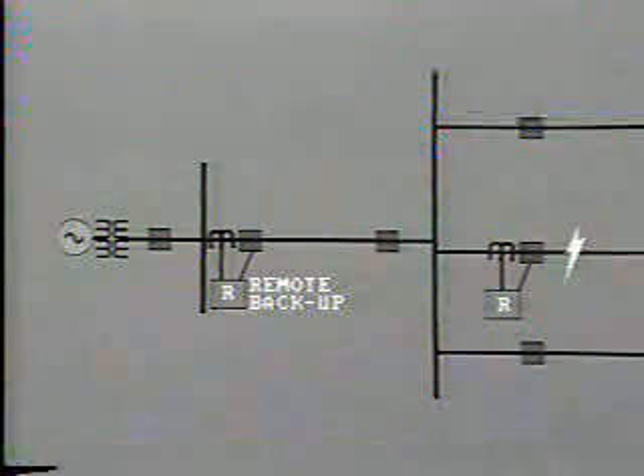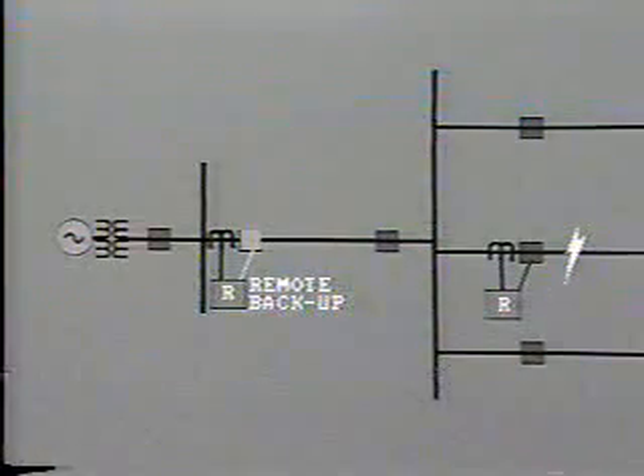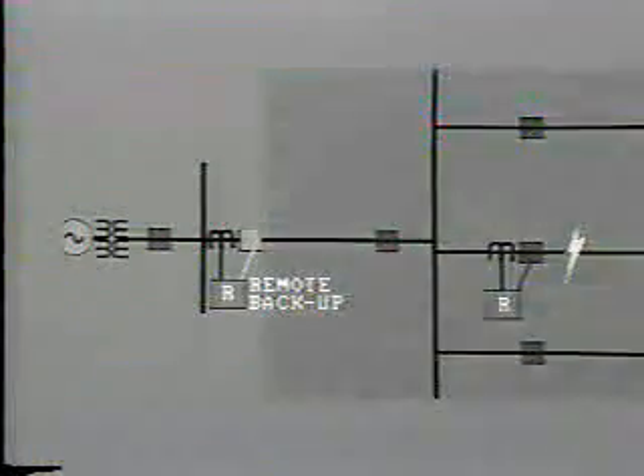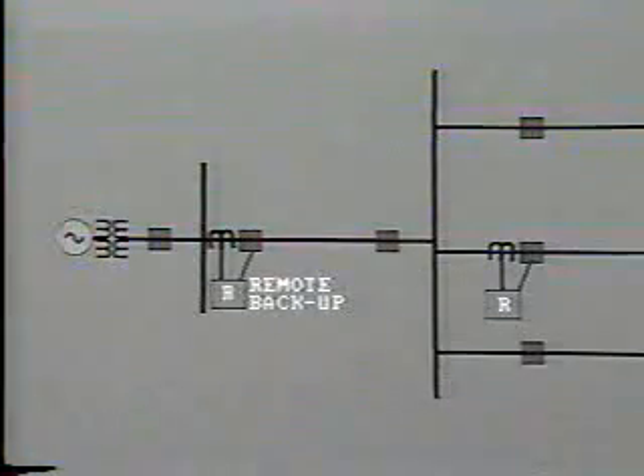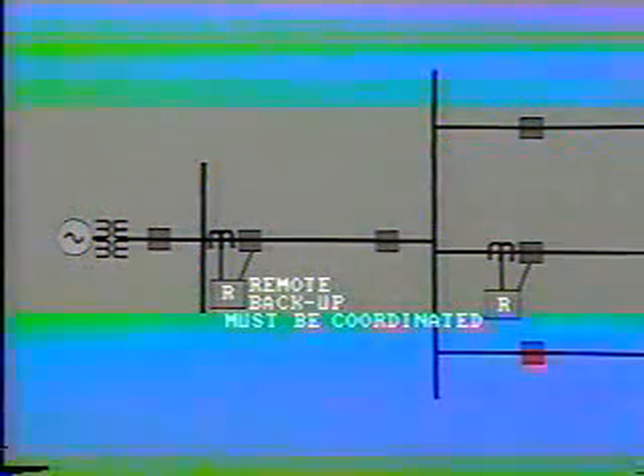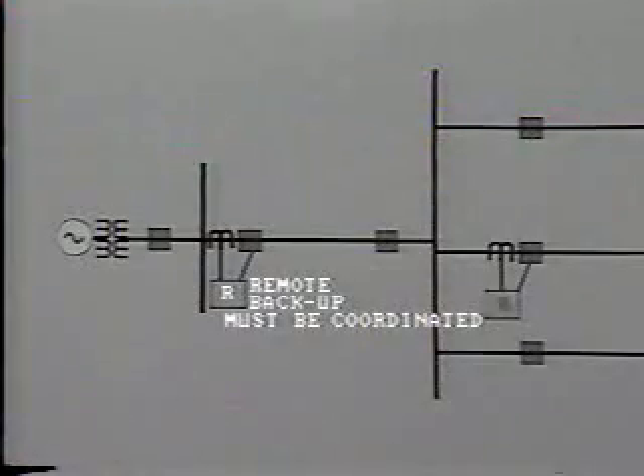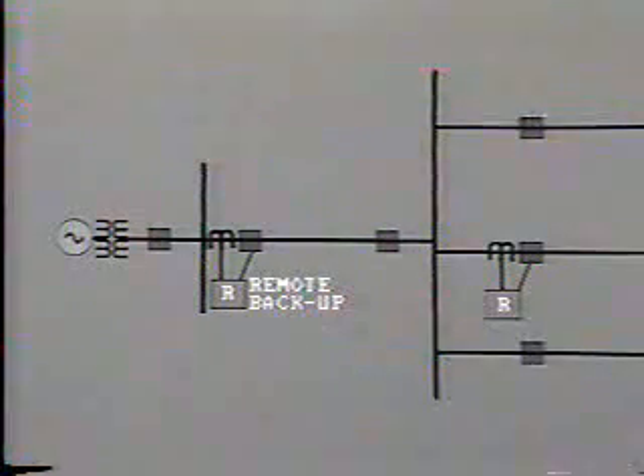Here we see the fault way out along the line, but the local protection fails to operate. The remote backup will then operate to open this breaker and so clear all of this line, as well as the bus and other outgoing feeders. When remote backup relays operate, they will generally isolate a larger area from the system and so cause a loss of power supply to more customers. The backup relays must be correctly coordinated so that they allow primary protective schemes to operate first. Only in the case of failure of the primary protection would the backup relays need to operate.